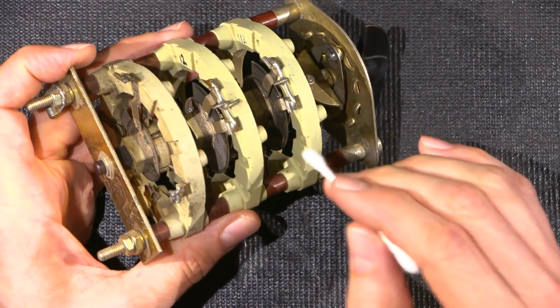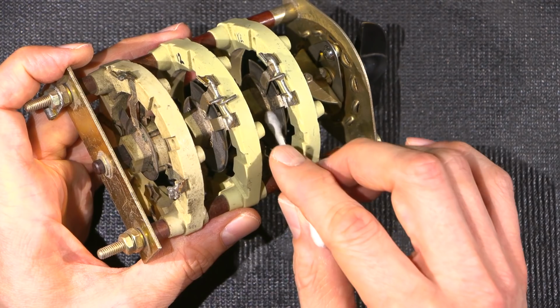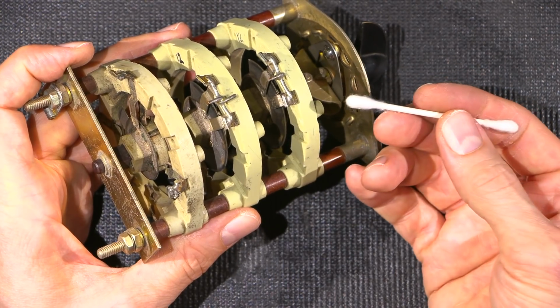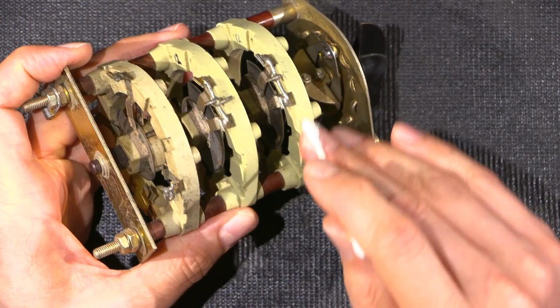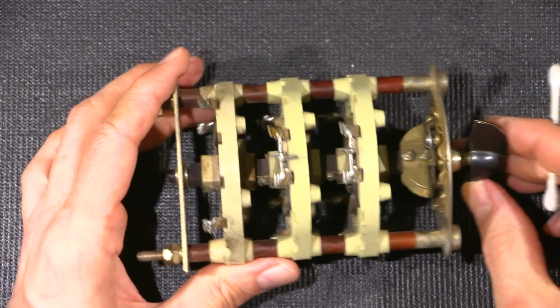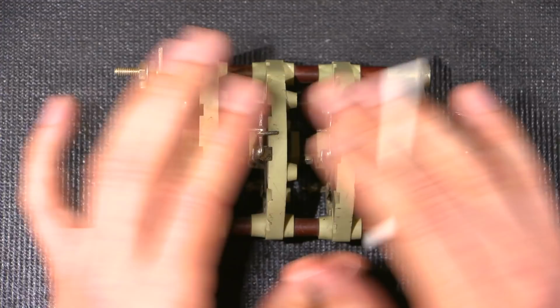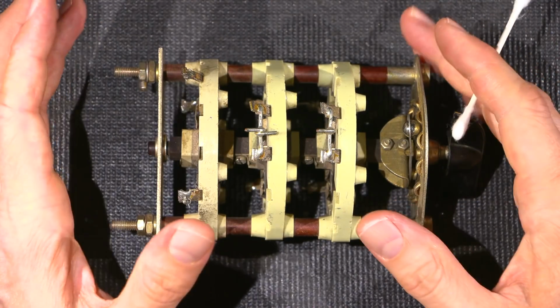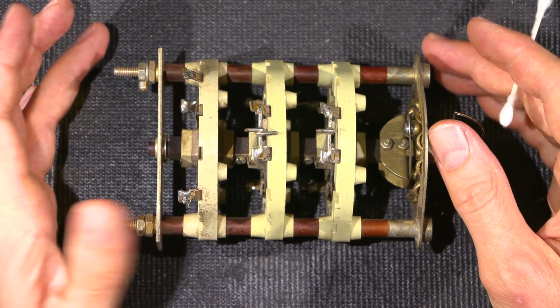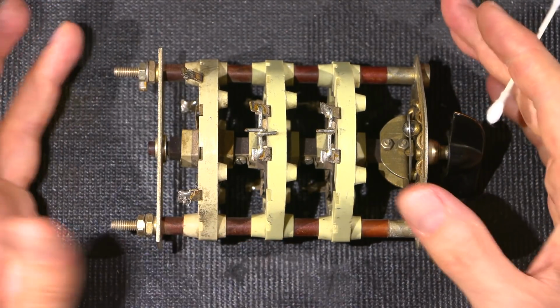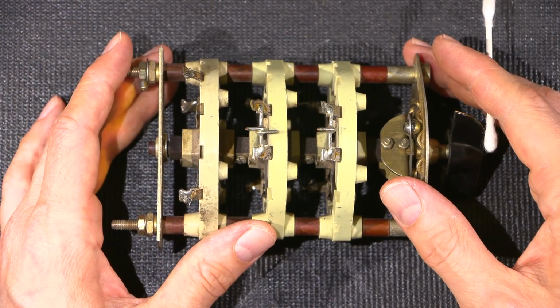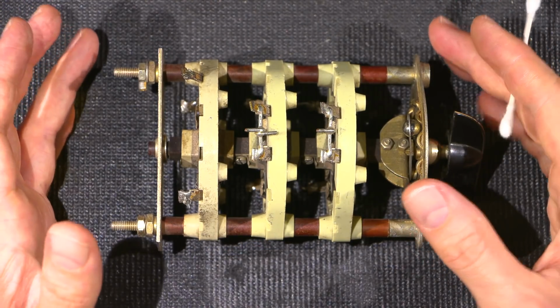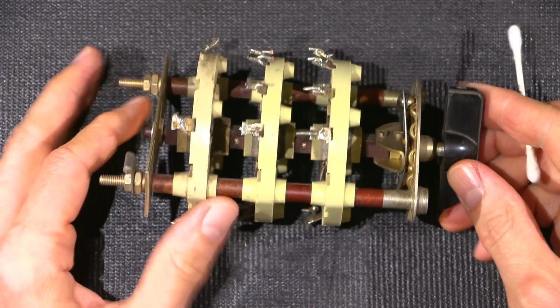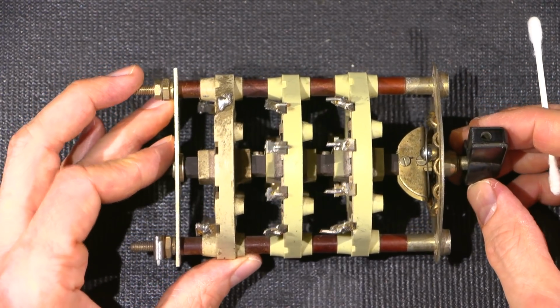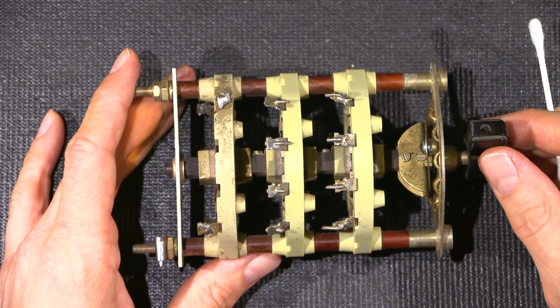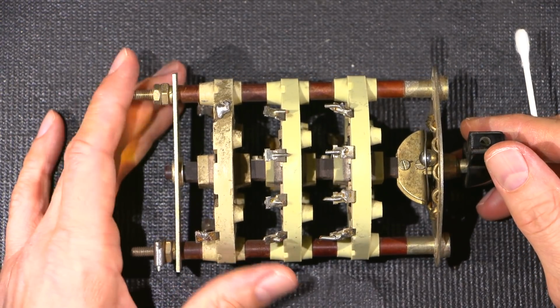As little as possible. Of course, a lot of the times there's a fibrous disc holding the contacts in the center. You can't avoid that, but you want as little on the actual discs as possible. Now, a lot of people get confused. They think, I've hosed down the whole switch and it's not drying up. Well, chances are somebody before you has sprayed some contact cleaner on it that has a light oil in it, and you're just noticing it. All right, so chances are the switch was probably soaked with an oily compound before. I find that DeoxIT will leave things just dry, and it does it with the toggle switches that I've cleaned.